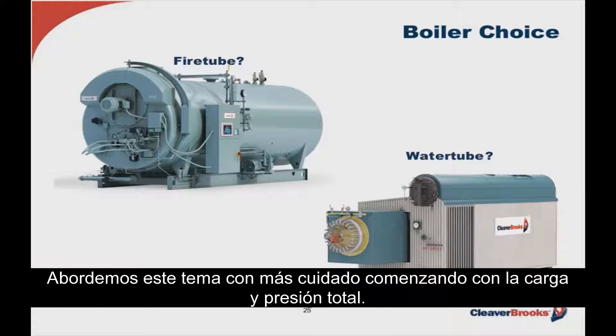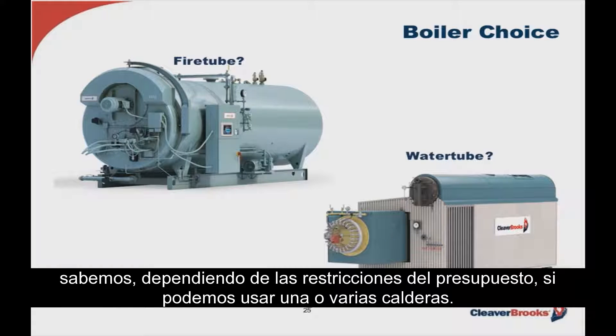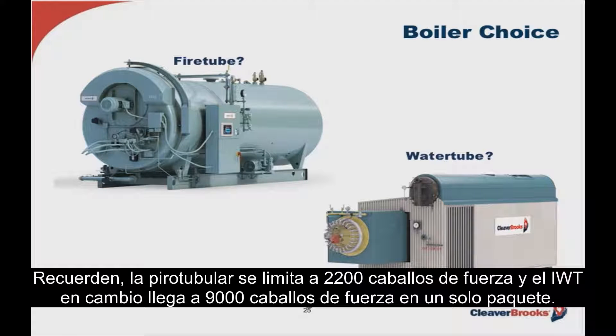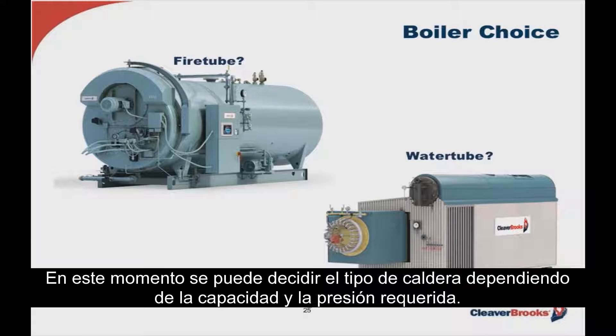Looking more specifically at total load and pressure: once we've determined the total load after the system is up to temperature and pressure, we know — depending on budget constraints — if we need one boiler or can afford multiples. Remember, the package fire tube is limited to about 2,200 horsepower, and the IWT can go to approximately 9,000 horsepower in a single package. As far as pressure, the fire tube tops out at approximately 250 pounds, whereas the water tube is about 900 pounds. So depending on capacity and pressure requirement, the type of boiler choice may be decided right here.